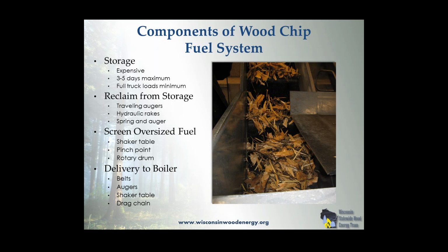Almost all the systems we put in, and certainly in institutional cases where we're required to meet some codes, we almost always have 100% redundancy in either a fossil fuel system or the existing system was in there, or we put in a new backup system that complements what we put in. And so it's not a disaster if you run out for a day or half a day. You're not going to spend that much more money in the total year's fuel use versus spending another $500,000 on fuel storage. So, it seems like it's a sticking point in every project, but the bottom line is that more than 3 to 5 days in the system is really a luxury and probably not needed and probably doesn't make any economic sense. You also have to design these systems so they'll take full truckloads.